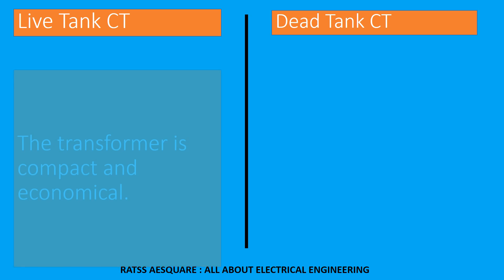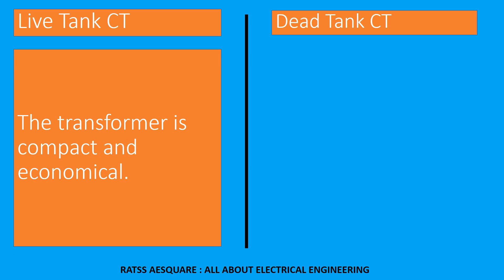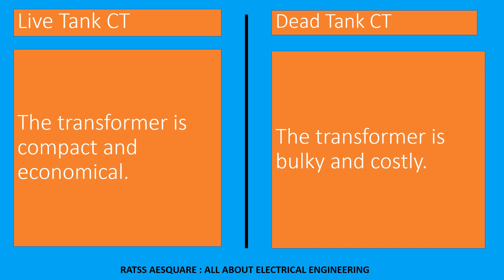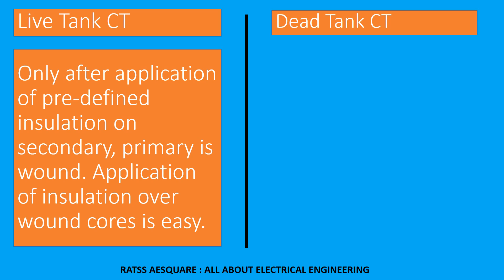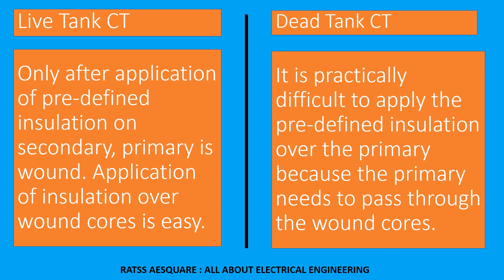The live tank transformer is compact and economical, while the dead tank transformer is bulky and costly. In live tank CT, only after application of predefined insulation on the secondary is the primary wound, and application of insulation over wound cores is easy. In dead tank CT, it is practically difficult to apply the predefined insulation over the primary because the primary needs to pass through the wound cores.